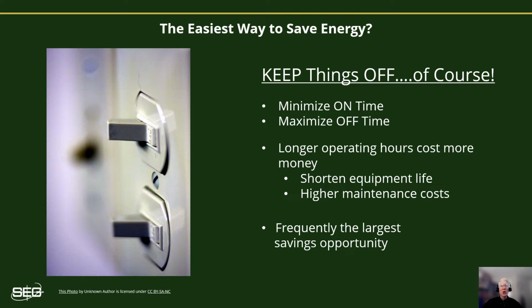Scheduling is often the largest savings opportunity, and it's very important to periodically review the current occupancy needs for the building and then compare that to the equipment schedules currently being used. Occupancy needs of buildings often change. Sometimes those changes will require longer equipment run times, so don't overlook an opportunity to cut back on operating schedules, even if it's for only a few minutes.